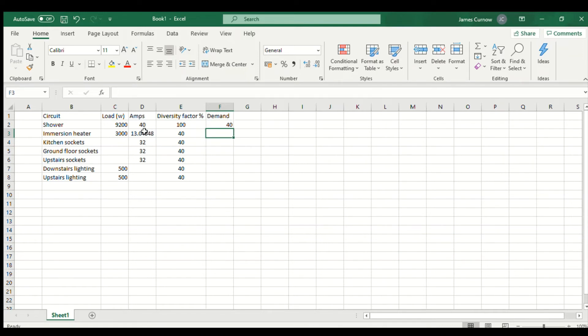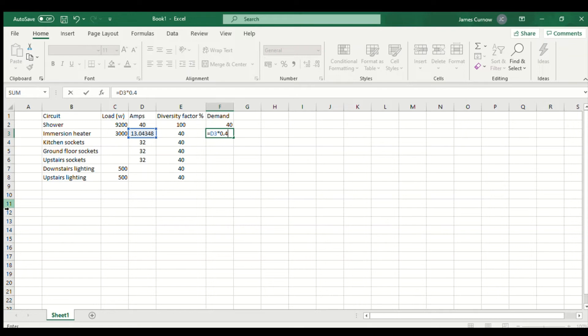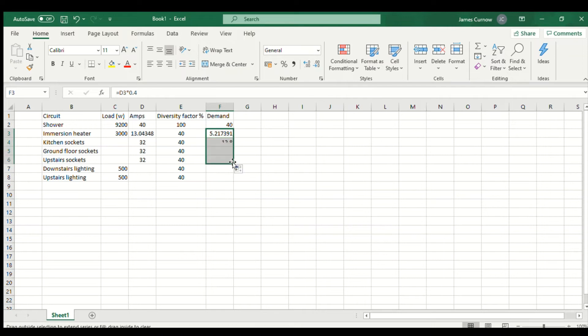For the remaining loads I'm going to multiply by 0.4 to give us 40%. So I type equals, click on the design current there, then asterisk for multiply and 0.4, and that gives us 5.2 amps for the immersion heater.